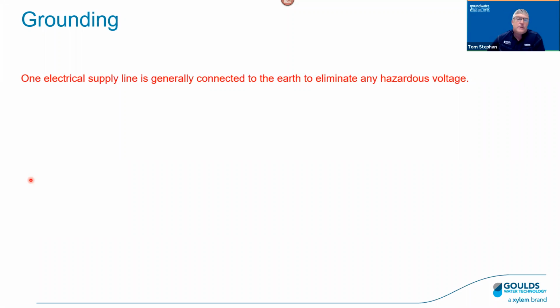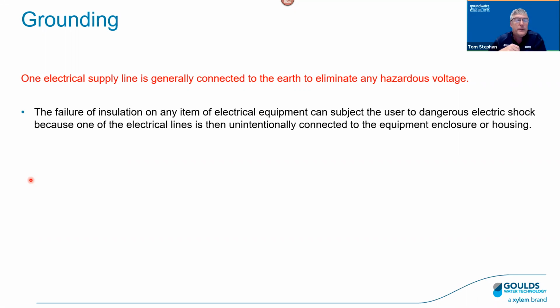Okay, grounding. Grounding certainly is a requirement by the NEC. And just a little bit here on grounding. One electrical supply line is generally connected to earth to eliminate hazardous voltage, so it's a safety issue. The failure of insulation on any item of equipment. So what we're talking about here is the insulation of the windings has gone bad, right? If that happens, it can subject the user to dangerous shock because one of the electrical lines is then unintentionally connected to the equipment, enclosure, or housing. So that's a shock hazard.